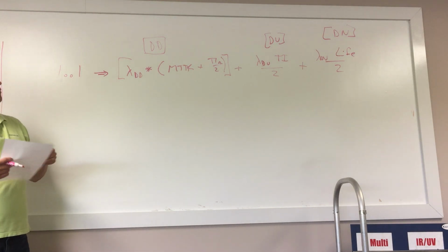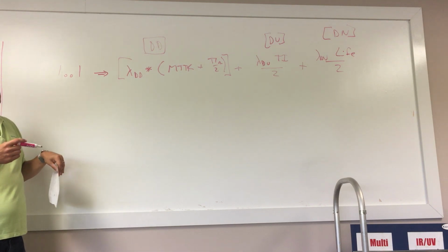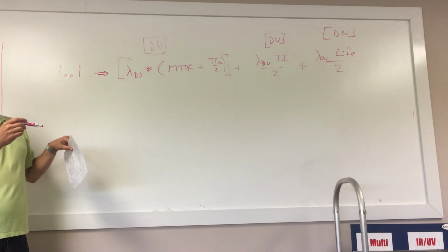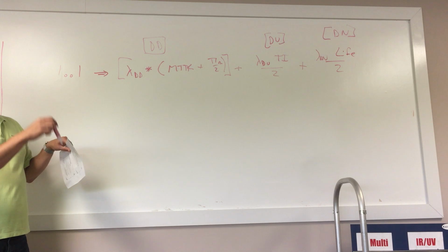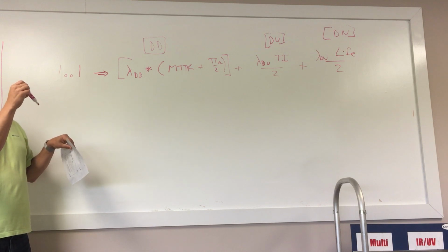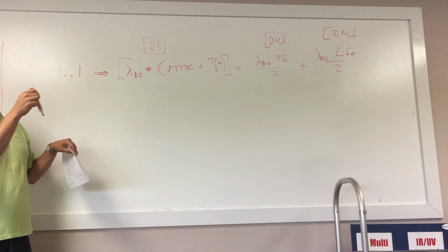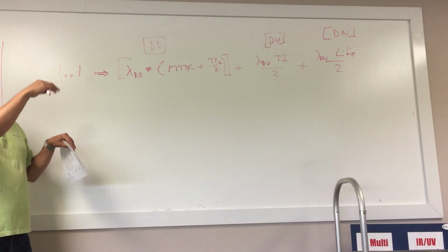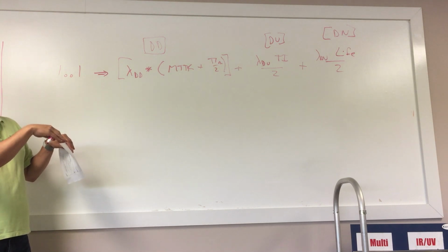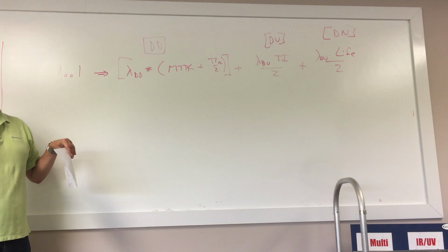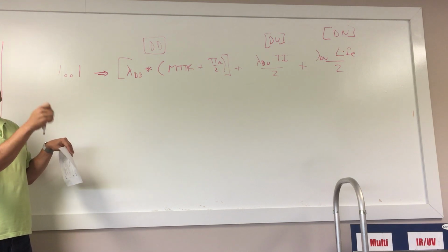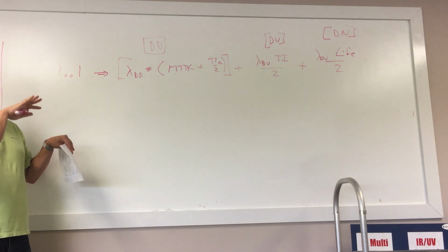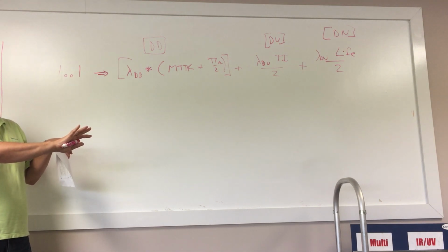So a good example of a never detected failure would be if I am using a diaphragm type actuator to move a shutoff valve, and that diaphragm starts to have pinhole perforations on it. That means that the pressured part is leaking through to the unpressured part, but only a little bit. Well, there's a point in time where those pinhole perforations are going to start to decrease the amount of force that that actuator provides.